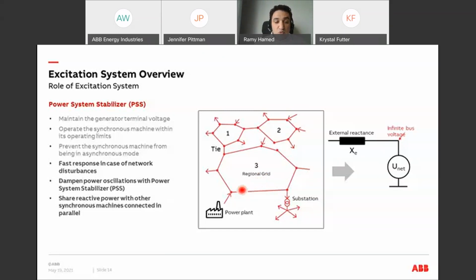And if these swings are not damped fast enough, the generator in your plant will trip, and the effect might propagate, and then you might end up with a complete blackout. And so the PSS function, the power system stabilizer, is implemented in the excitation system to immediately act after the system event and dampen the power swings or oscillations and make the unit more stable and consequently the grid more stable.